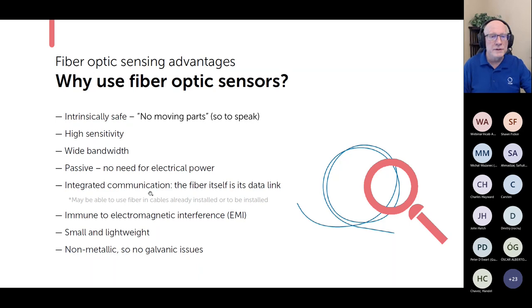You've got integrated communication. So the fiber itself is not only the sensor, it's also its own data link. And because of that, you may already be able to implement various types of fiber optic sensing in cables that you already have installed or that you're planning to install in the near future. Fiber optic sensors are immune to electromagnetic interference. They're small and lightweight. And in general, they're non-metallic, so you don't have galvanic issues like you do with some types of sensors that you might put underground. But of course, if you end up using an armored cable, a metallic armored cable, well, that's a different story. But yeah, I probably should update that a little bit.